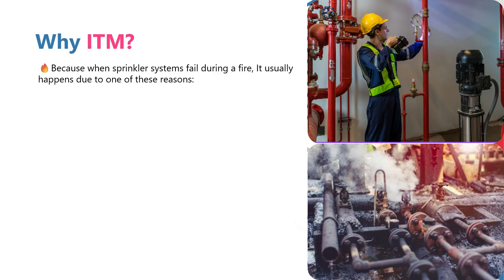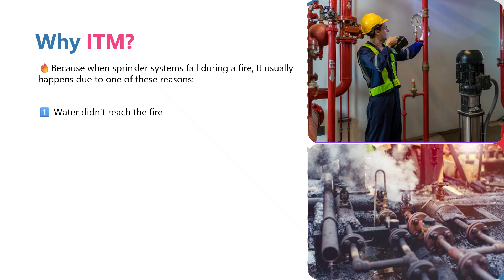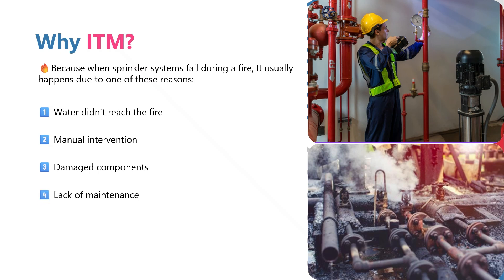When a system fails during a fire, it usually happens due to one of the following reasons: water didn't reach the fire because someone left a valve closed, or manual intervention where a repair was done but the valve wasn't reopened; damaged components like a corroded sprinkler head or broken pipe; or lack of maintenance — dust, debris or aging parts that were never tested. That is exactly why NFPA 25 exists — to prevent these failures before a fire happens. Bottom line: even a perfectly installed system can fail if it's not properly maintained.